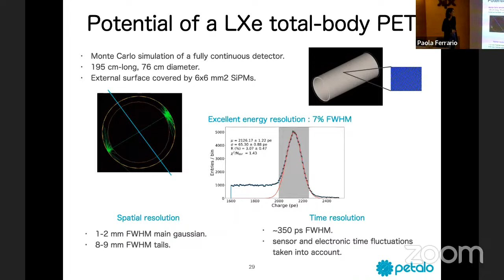But of course, we also have events where a Compton interaction happens, so you have 2 different interactions of the gamma in xenon. So the response on your silicon PMs is more complicated and you make a bigger error, around 8-9 millimeters full width at half maximum. We also estimated the energy resolution that we could achieve, and we found an excellent energy resolution of 7% full width at half maximum. And finally, the time resolution that we can achieve with this kind of scanner is also very good, 350 picoseconds full width at half maximum, also having taken into account all the fluctuations that you have in a real detector. So the sensors have time fluctuations, the electronics, all of this is taken into account.